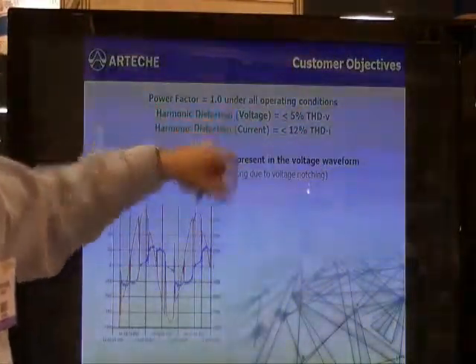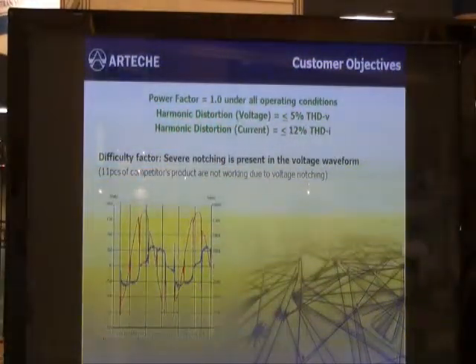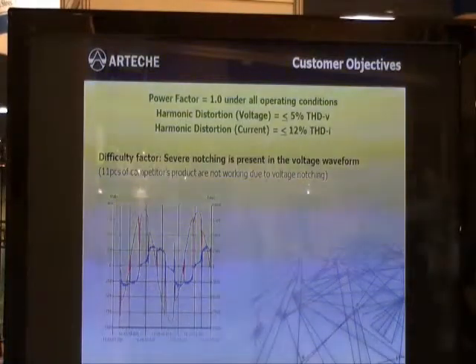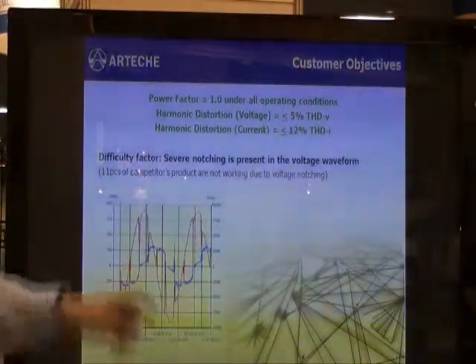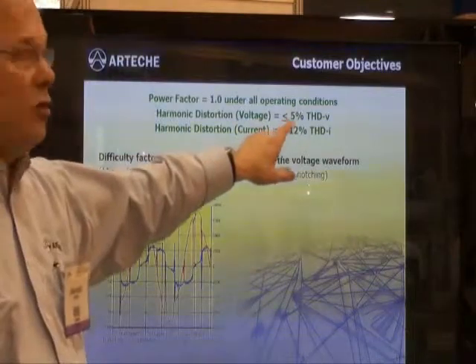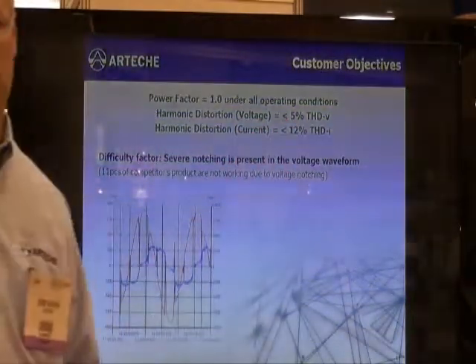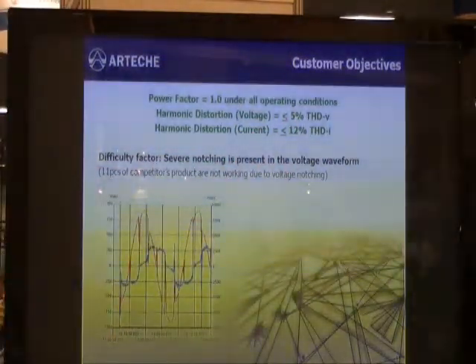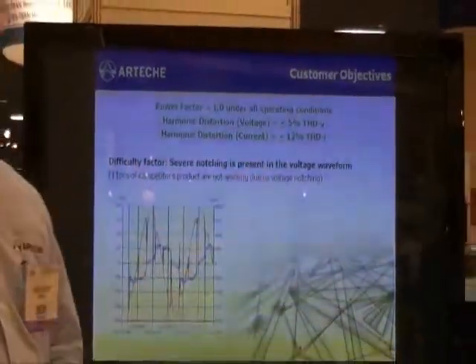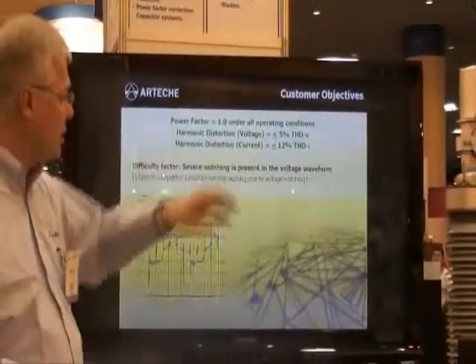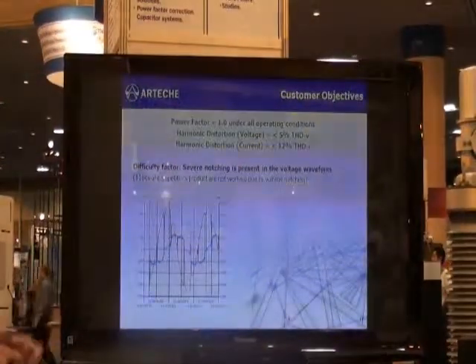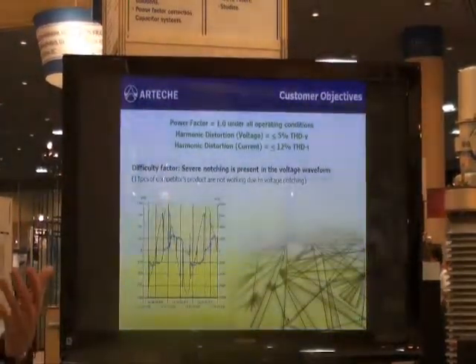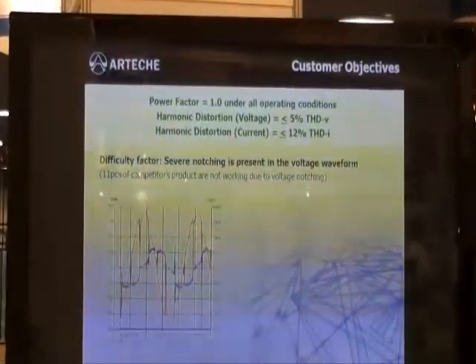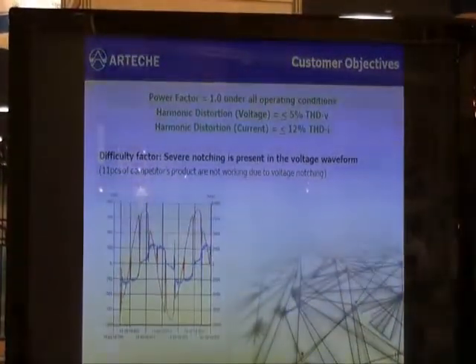The customer objectives in this case were to maintain nearly 1.0 or unity power factor under all of the various operating conditions and loads, to achieve and maintain a voltage distortion of 5% or less, and to maintain current distortion less than 12%. So based on those customer objectives, our engineers looked at the load profile situation and made a recommendation.